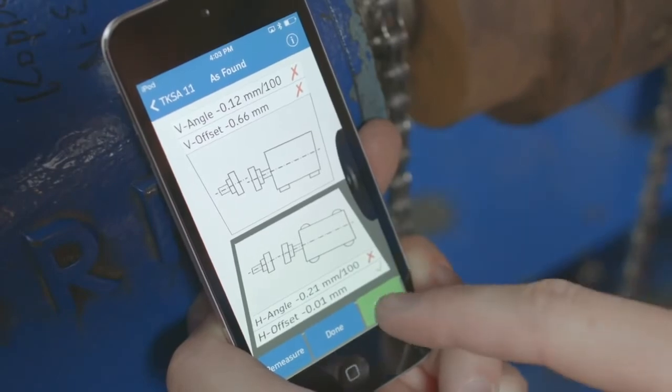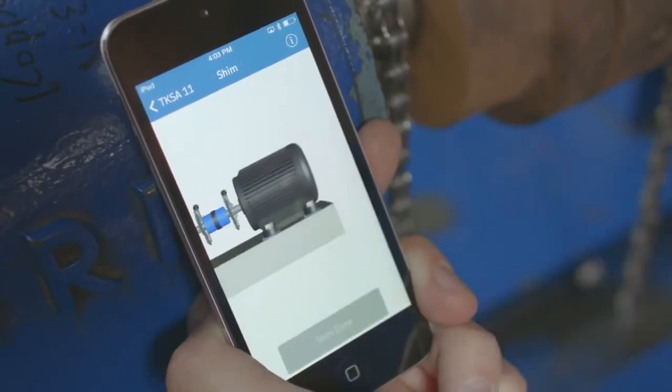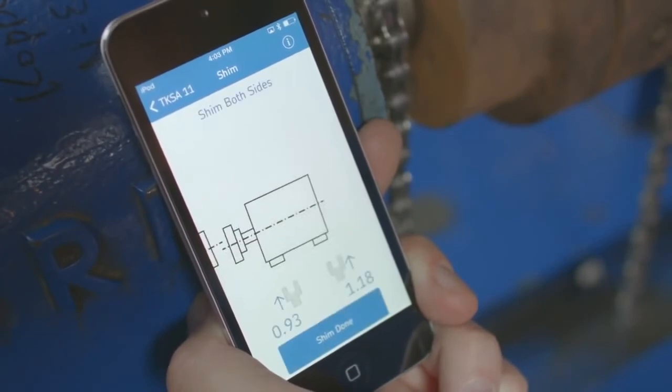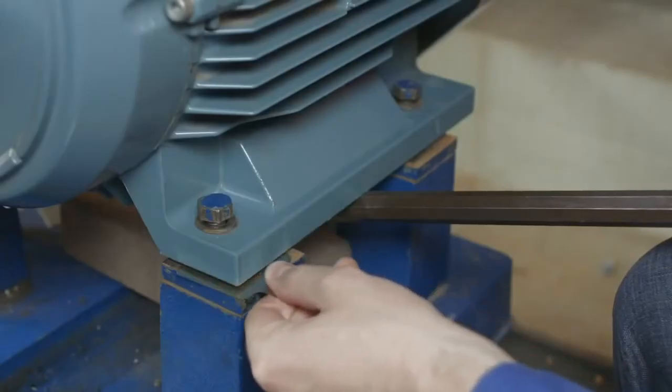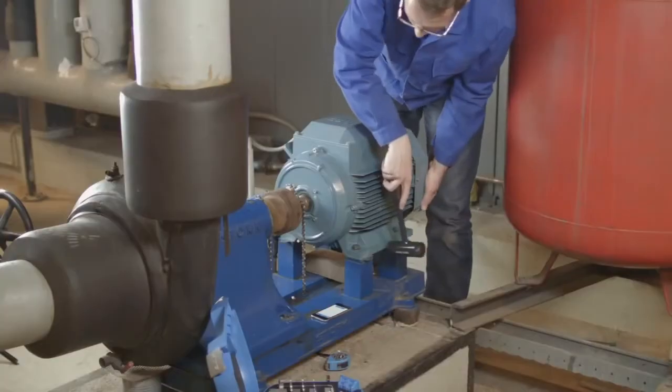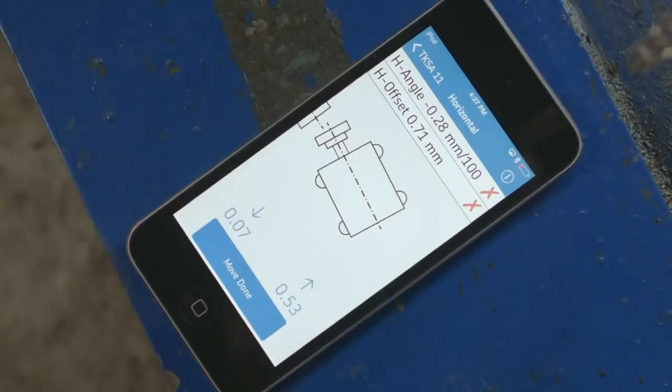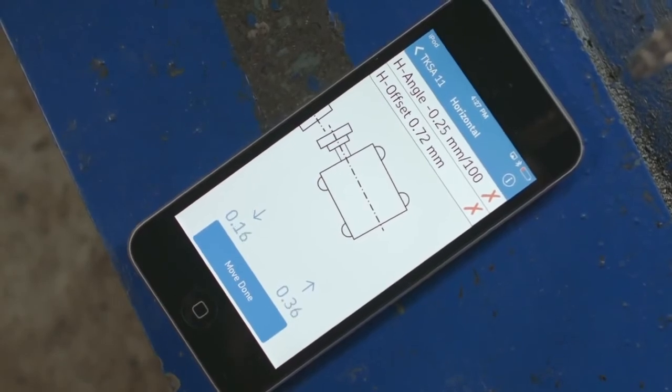After determining the current shaft misalignment, the app guides you through the alignment process. First, by showing what shims are needed for the vertical alignment and then which movements need to be performed for horizontal alignment. The live view helps you quickly achieve accurate positioning.